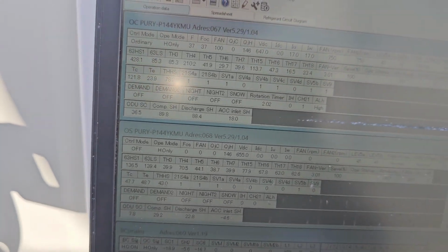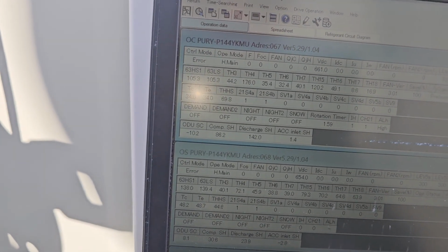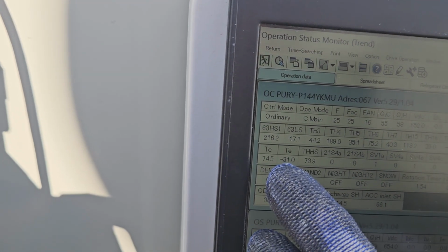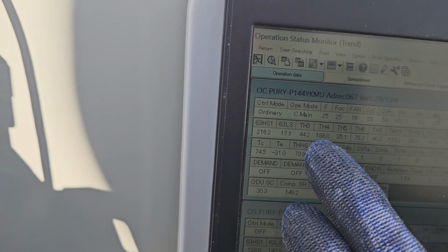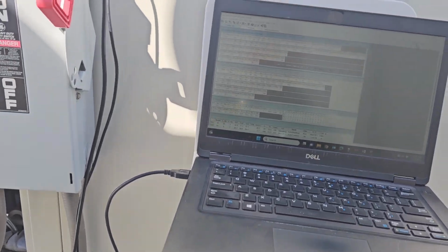So in the beginning, when I first started watching this, I was thinking, oh, definitely looks low. We have low condensing temp, low evap temp, high TH4. That's very indicative of a low charge. That compressor's going to run hotter. You're not going to really be able to build pressure, all that. But as I've stated many times, you need to be able to sit and have patience and watch this. If you determined that this was low on charge after this amount of time, you'd be wrong, because it's not low.